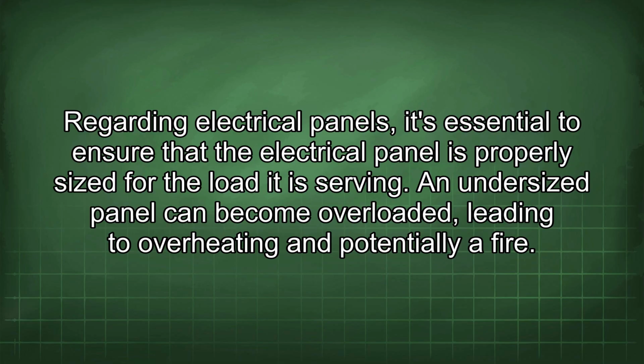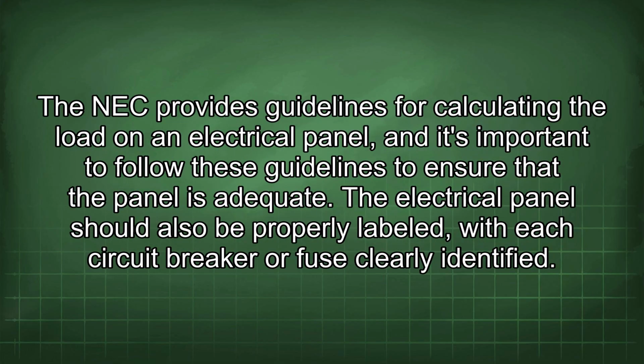Regarding electrical panels, it's essential to ensure that the electrical panel is properly sized for the load it is serving. An undersized panel can become overloaded, leading to overheating and potentially a fire. The NEC provides guidelines for calculating the load on an electrical panel, and it's important to follow these guidelines to ensure that the panel is adequate.